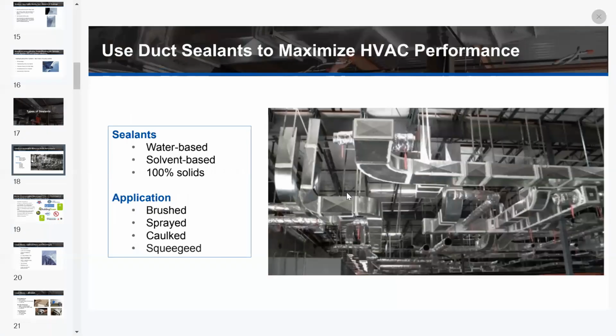All right, so we'll talk about the different types of sealants. There are several options to choose from when selecting a duct sealant, depending on the size of the project and the time commitment it will take. Mastic comes in typically water-based and solvent-based and can be either brushed on or sprayed on. Another option is to use a 100% solids product known as a rolled mastic sealant. It looks similar to duct tape, but make no mistake, there is no comparison.